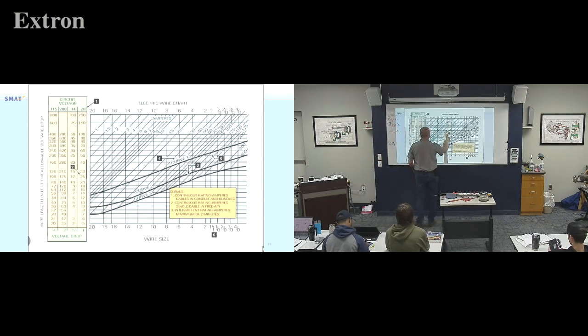10. Christina has gone over all these with us before. All right. 10 amp. I come down. I think I'm in the neighborhood somewhere between 14 and, oh, we switched over to continuous use, which is why the number's slightly different, but the point will come across. So we'd come down and say somewhere between 14 and 16 gauge on this one. And then we'd one more time double check my 10 coming across and make sure it doesn't hit the curve. Curve 1 is continuous rating in conduit and bundles. 2 is continuous in single air, and 3 is intermittent.